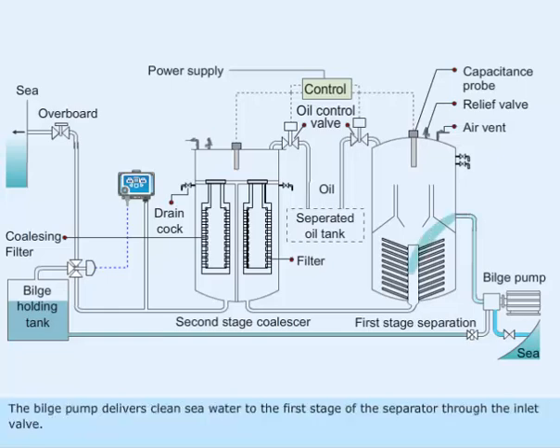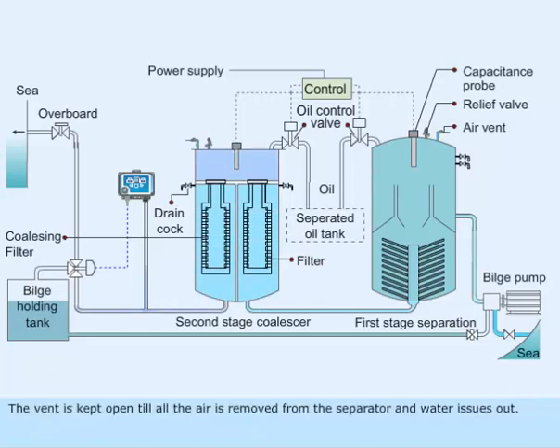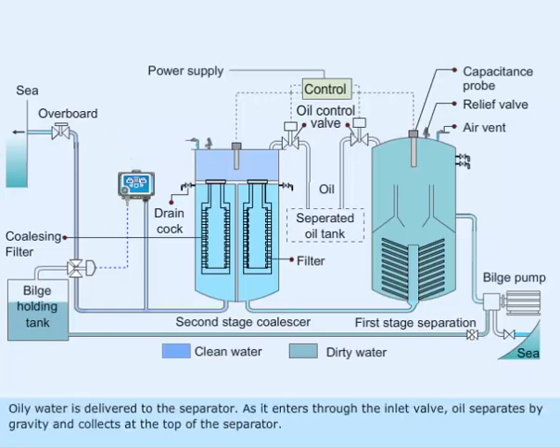The bilge pump delivers clean sea water to the first stage of the separator through the inlet valve. The vent is kept open till all the air is removed from the separator and water issues out. Oily water is then delivered to the separator. As it enters through the inlet valve, oil separates by gravity and collects at the top of the separator.